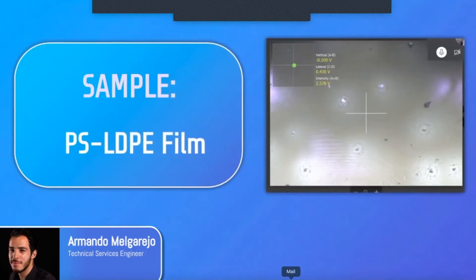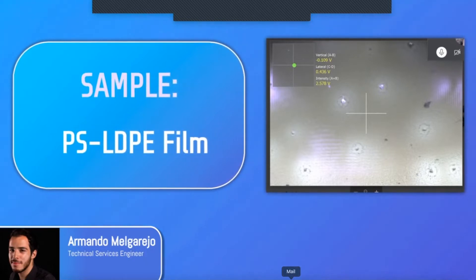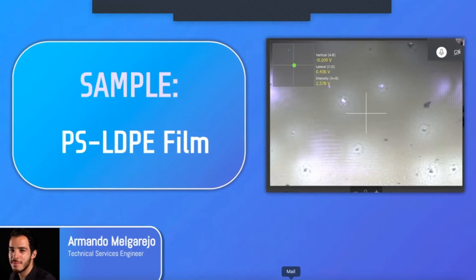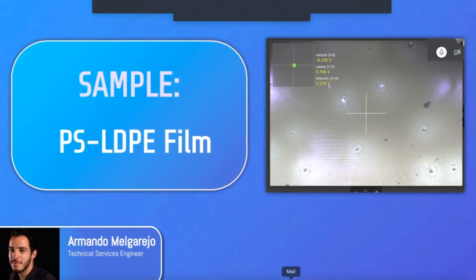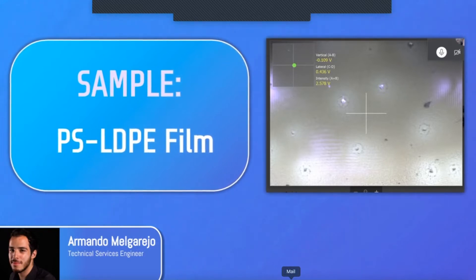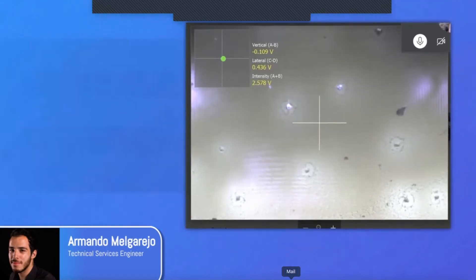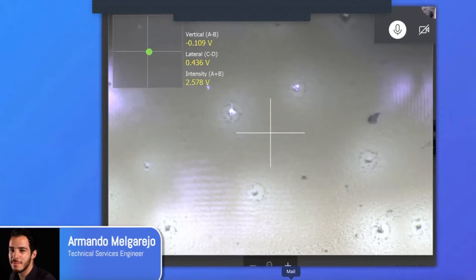For this demonstration, I'll use a polymer blend sample called PSLDPE, polystyrene low-density polyethylene, where one material, the polystyrene, is about 20 times harder than the low-density polyethylene. Low-density polyethylene has a hardness of about 100 MPa. Given the relatively wide range of hardness, the polymer sample serves as a calibration reference for samples with a hardness within a few MPa to tens of GPa.